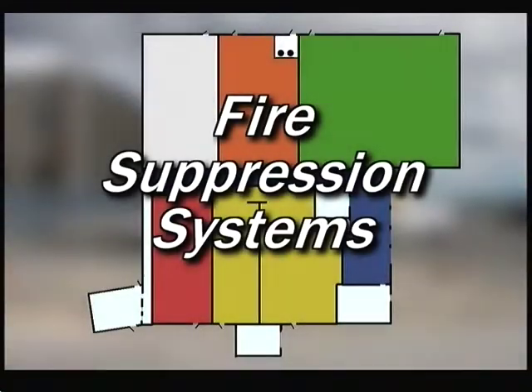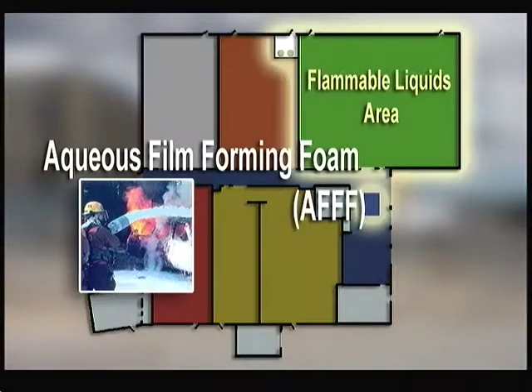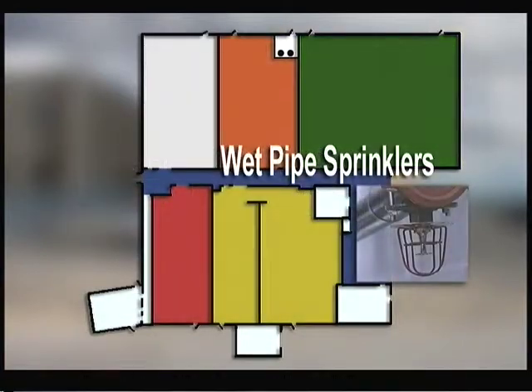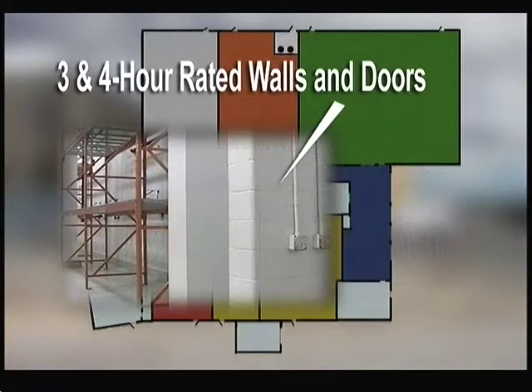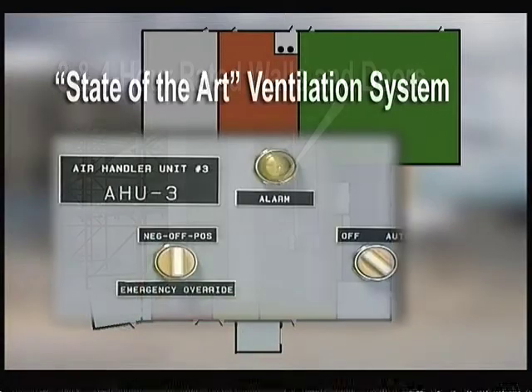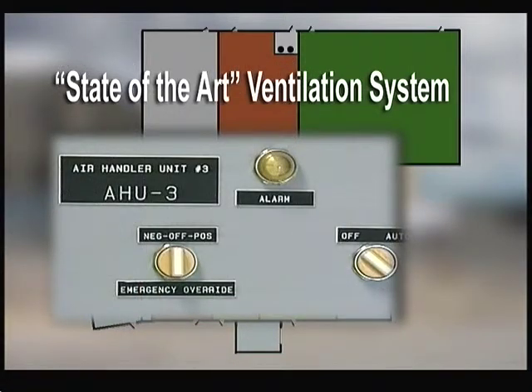The facility has complete fire suppression coverage throughout all areas. Systems include an AFFF foam extinguishing system for the flammable liquid storage area and wet pipe sprinkler system protection in other areas. Each hazard room is self-contained with 3 and 4 hour rated walls and doors. The heating and ventilation system is state-of-the-art, allowing up to 6 air changes per hour and reacting to self-contain any room with a problem and isolating it from the rest of the facility.